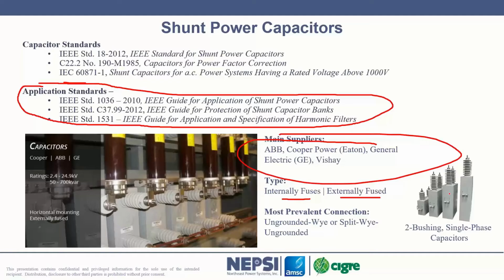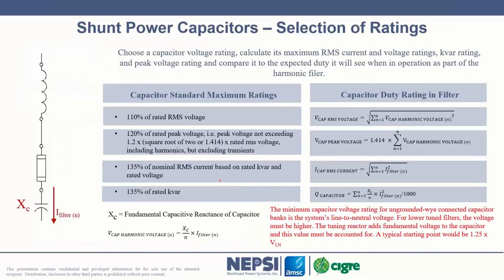It's really a geographical based system. I believe Australia is more involved in using internally fused capacitors, where in North America we are almost always using externally fused capacitors. I can argue why externally fused capacitors are better than internally fused capacitors, and I'm telling you, you can find somebody out there who will argue equally as strong about internally fused capacitors being better than externally fused capacitors. So I say stick with what's normal in your territory. If internally fused capacitors are being used in Australia, then continue to use those because it's the typical one; one's about equal to the other.